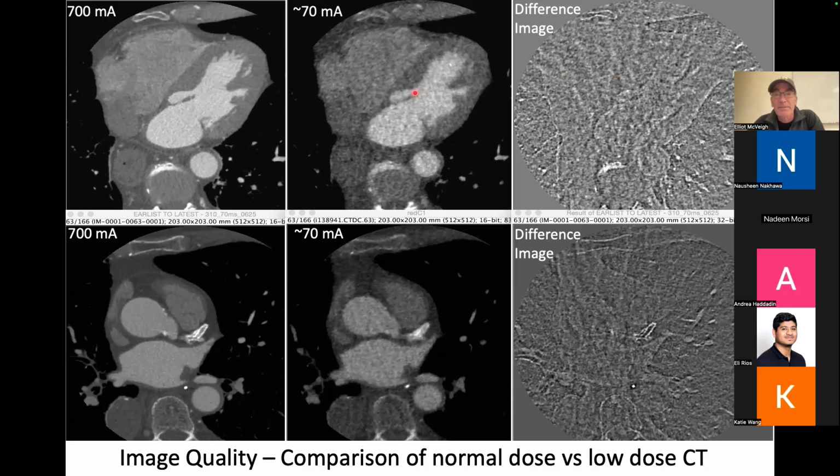And the reason for that is that the manufacturer, when they look at the sinogram that produces this, sees that the sinogram itself doesn't look good. And they say, oh, we need to fix this. We need to smooth it. There are even detectors that have too few counts. We need to paint artificial counts in there just so that the noise doesn't totally explode.